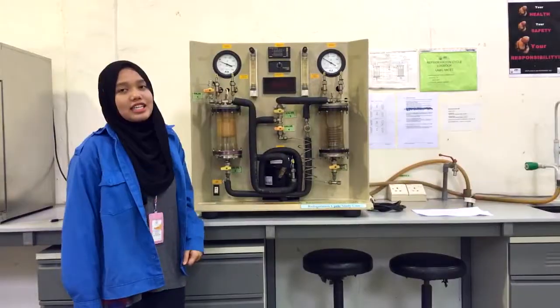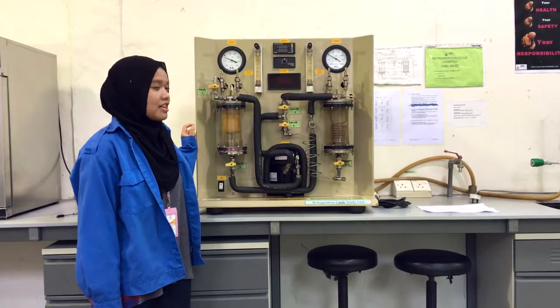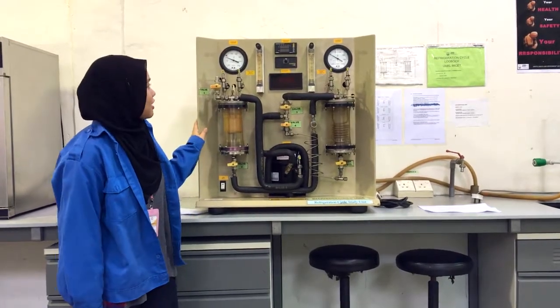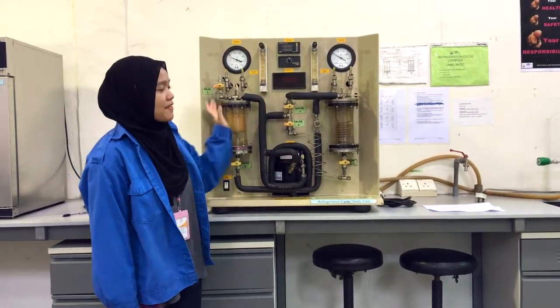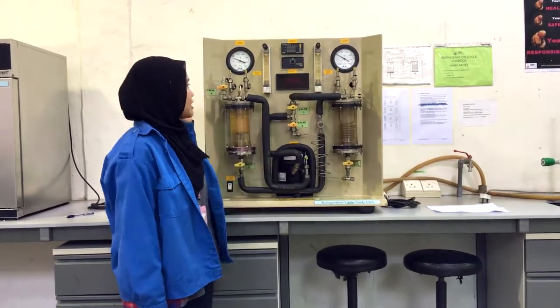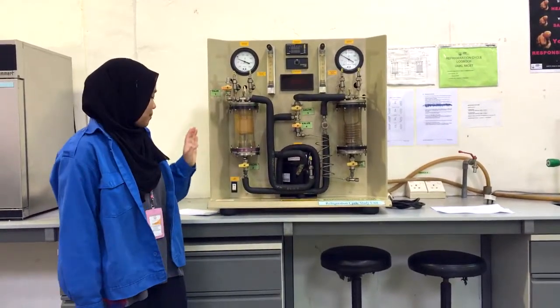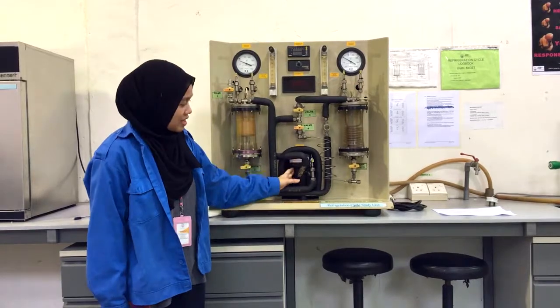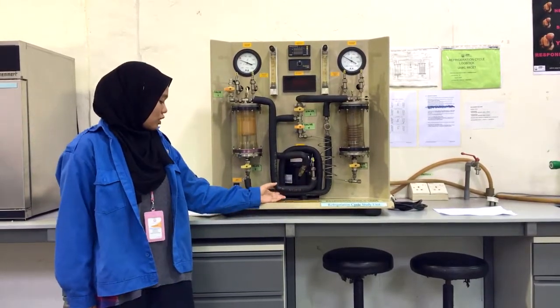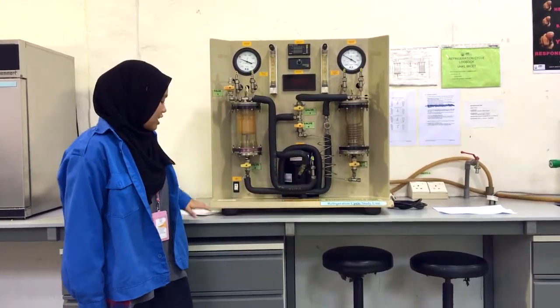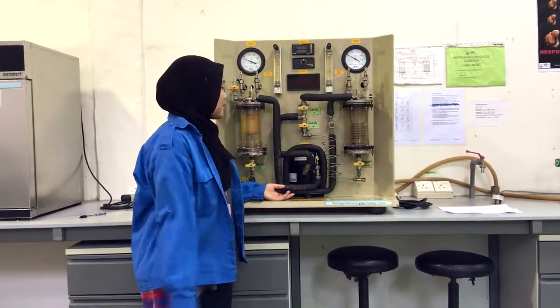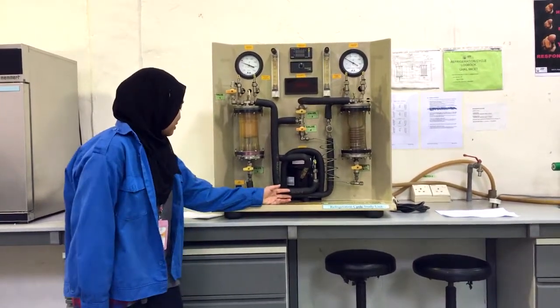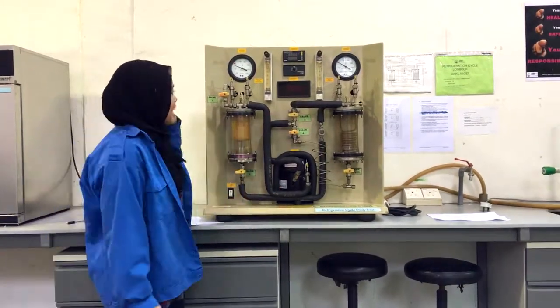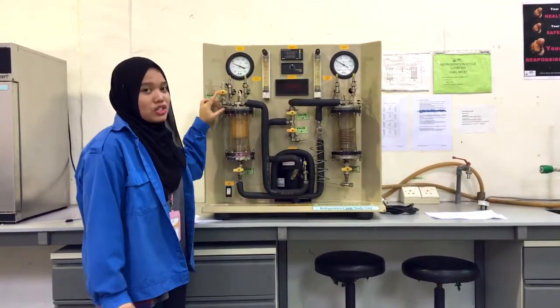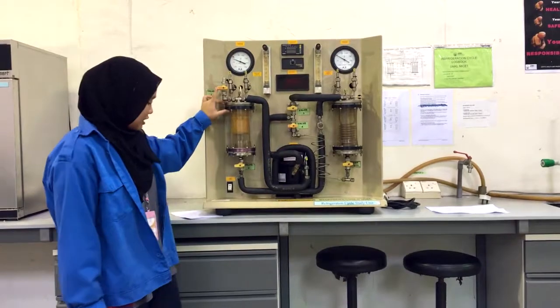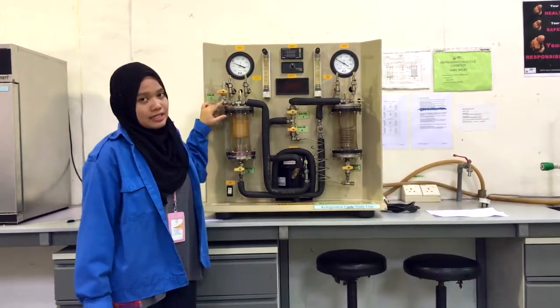This is the refrigeration system of the lab scale machine. First, we have the condenser, evaporator, compressor, and expansion valve. The compressor is used to reduce the pressure in the evaporator and increase the pressure of the vapor being transferred to the condenser. The expansion valve is used to control the flow of liquid in the refrigeration and reduce the pressure.